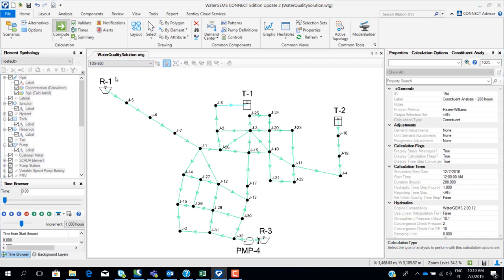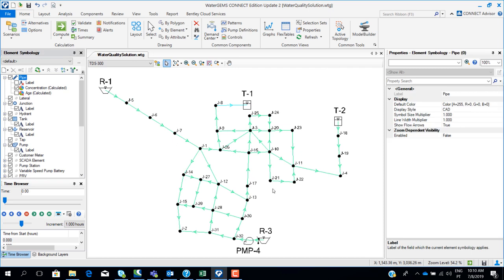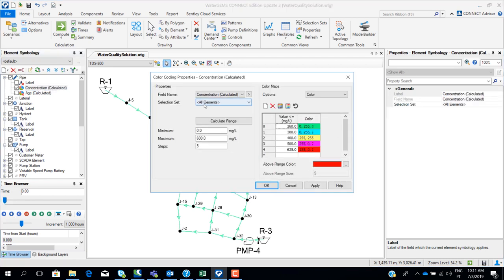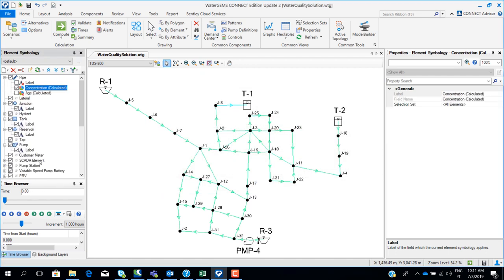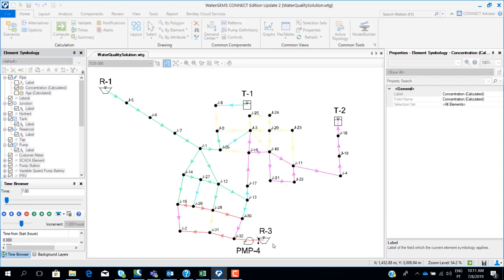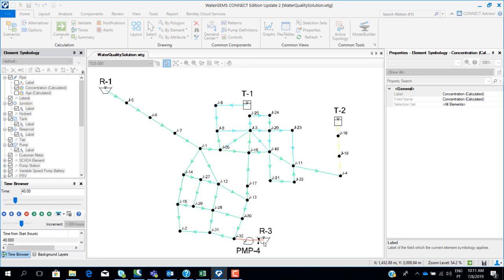We can run this scenario and see how the total dissolved solids will disperse in the network over time. As you can see, over time the total dissolved solids spread across the network. Since the sources are the reservoirs and tanks, it is normal to have higher concentrations near those. Reservoir one has lower concentrations, which is why it shows green.